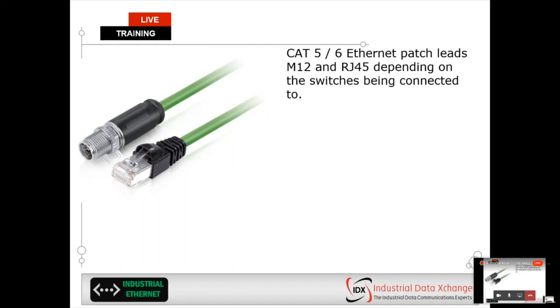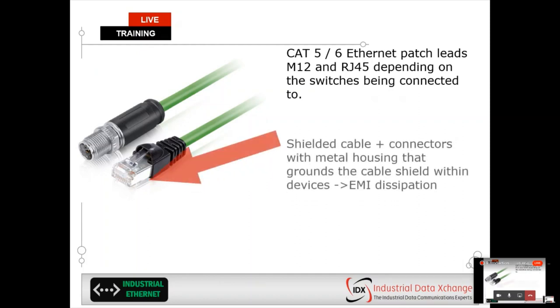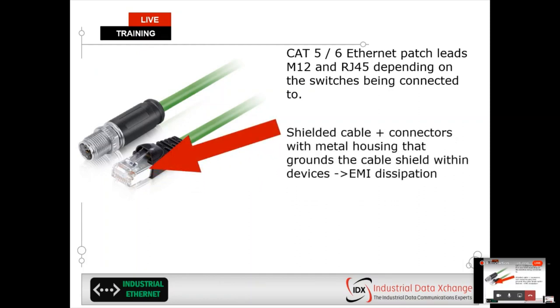The first one is actually utilizing the proper industrial Ethernet cable spec for the system you want to install. For example, PROFINET requires Cat5e cable, which is a four-core twisted shielded cable, and very important is the shielding.